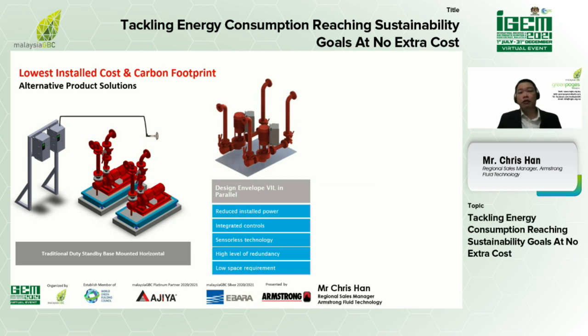So this is where you evolve from traditional duty standby horizontal pumps with variable speed drives on the wall to sensorless vertical inline pumps in parallel, where you're talking about two duty pumps in parallel. When you consider that evolution, you also have a reduction in installed power, electrical infrastructure savings, and installation savings with integrated controls and sensorless technologies.